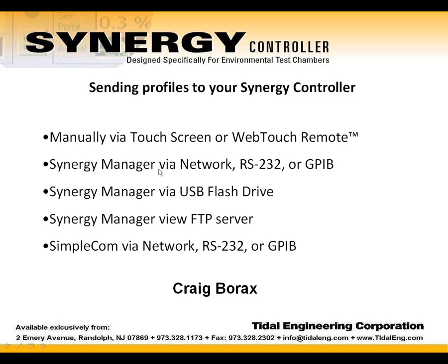With the full version of the software, you can then transmit the profiles through your network or via RS-232 or GPIB to your controller. Or without the full version, you can copy the profile to a USB flash drive, walk it over to your controller, and load it up from the program screen. You can also drag a profile edited on your PC with Synergy Manager to the controller's built-in FTP server. And finally, you can send the profile step by step by transmitting it through your network, RS-232 or GPIB interface. Let me do a quick demonstration of some of these methods.